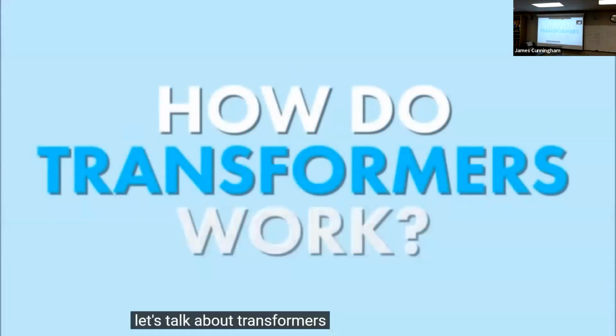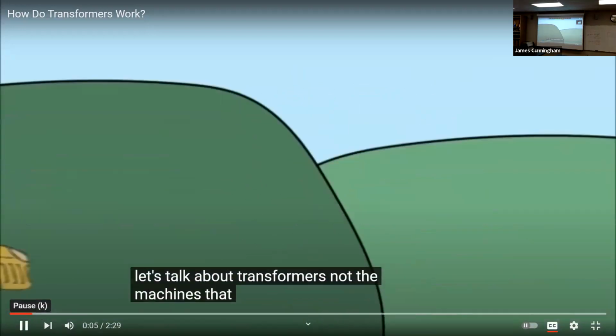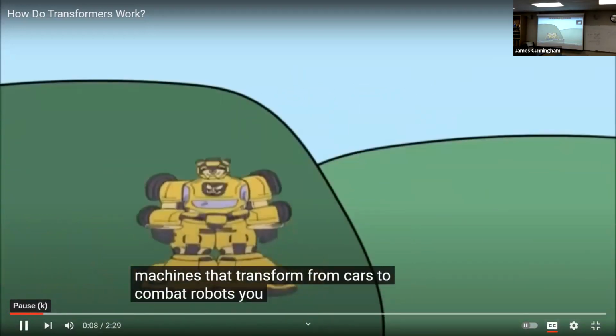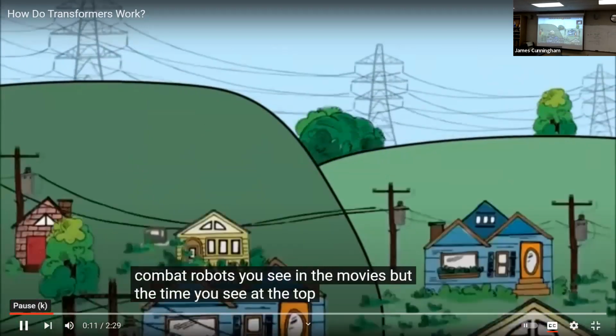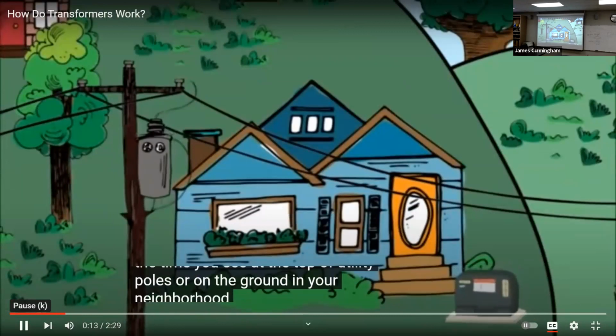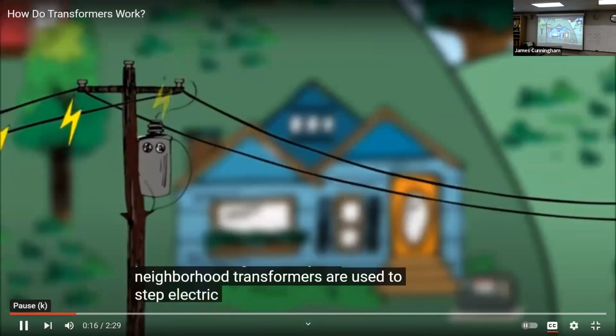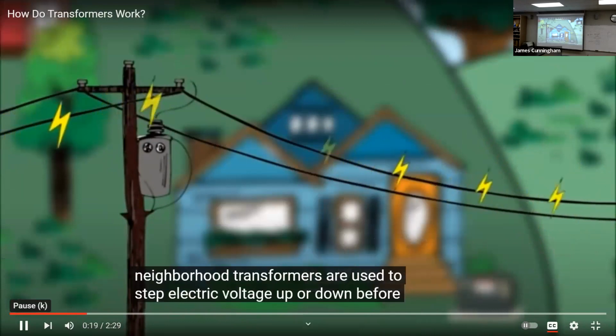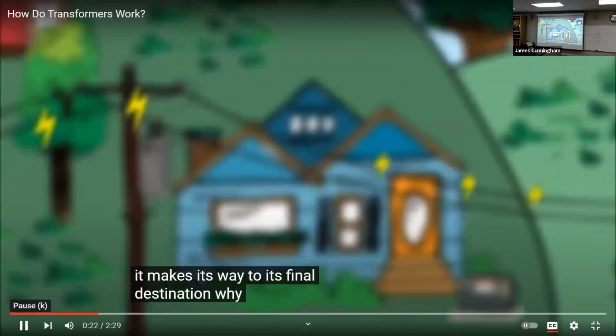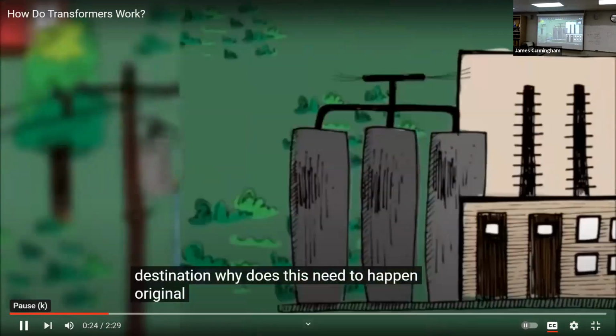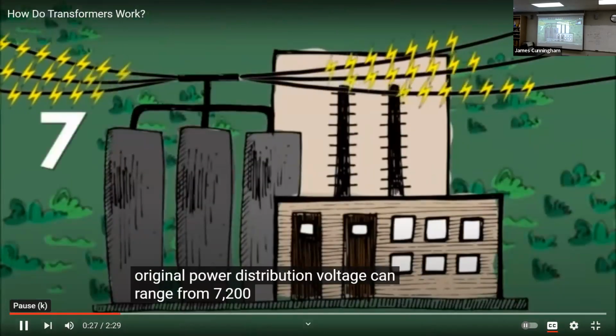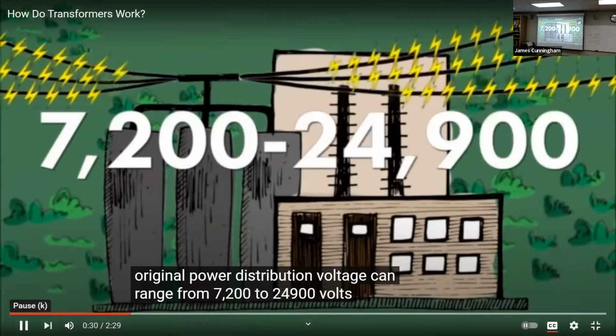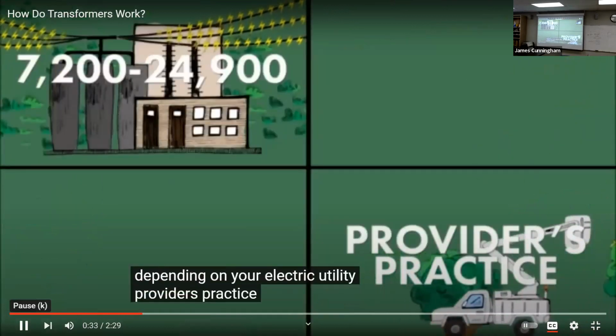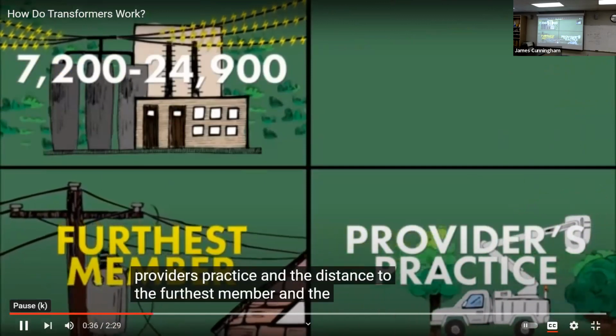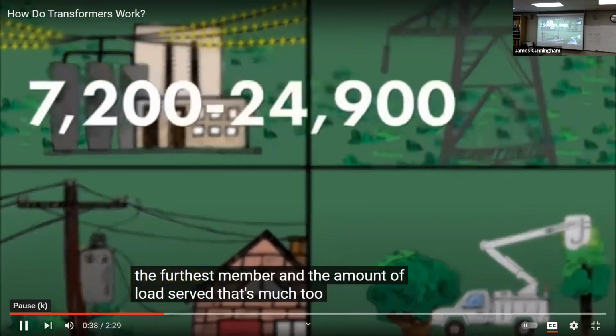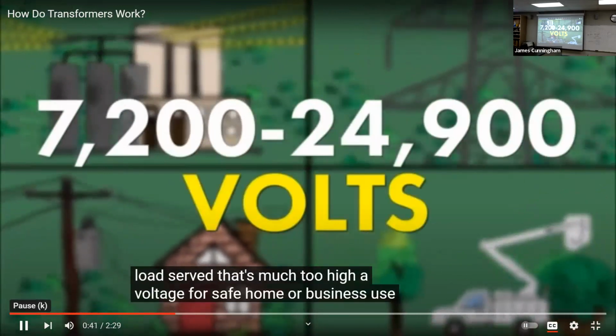Let's talk about transformers. The machines that transform cars to combat robots you see in the movies, the kind you see at the top of utility poles or on the ground in your neighborhood. Transformers are used to step electric voltage up or down before it makes its way to its final destination. Why does this need to happen? Original power distribution voltage can range from 7,200 to 24,900 volts, depending on your electric utility provider's practice, the distance to the furthest member, and the amount of load served. That's much too high a voltage for safe home or business use.